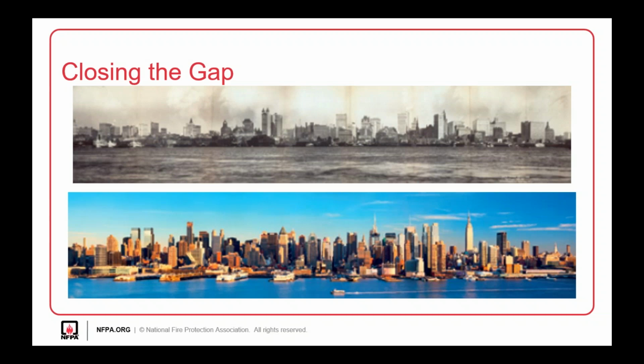Keep in mind, although NFPA 4 was new in 2015 as a standard, integrated system testing is certainly not a new concept. In the 1930s, the highly protected risk insurance industry needed to ensure fire sprinkler activations were acted upon in a timely fashion. Shortly thereafter, NFPA 71, the standard on central station service, required the inspection and testing of sprinkler water flow valves, which were required to be monitored per the listed central station.